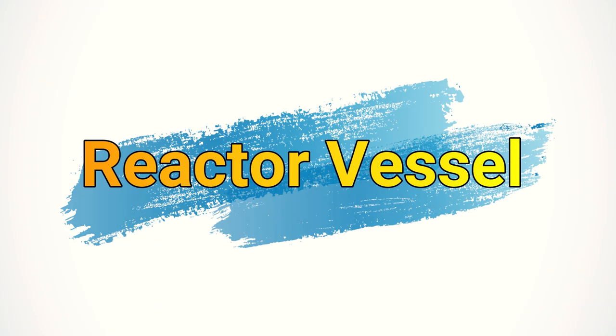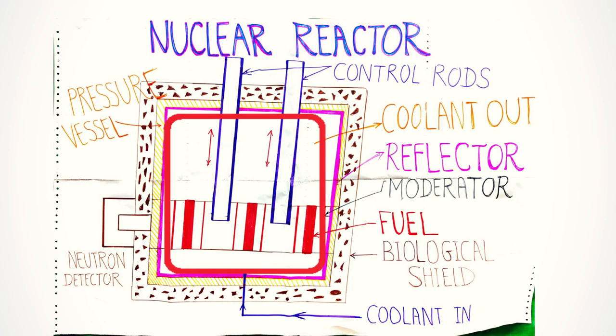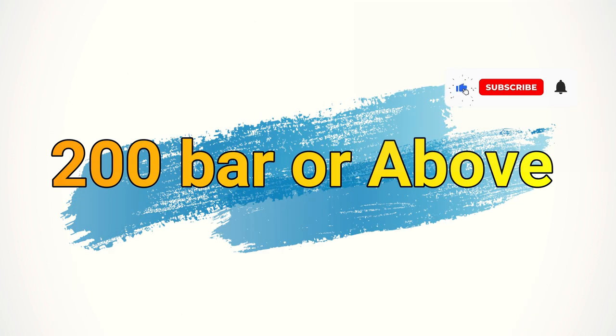The next one is reactor vessel. The reactor vessel encloses the reactor core, reflector, and shield. It also provides the entrance and exit passage for directing the flow of coolant. The reactor vessel has to withstand pressure as high as 200 bar or above.